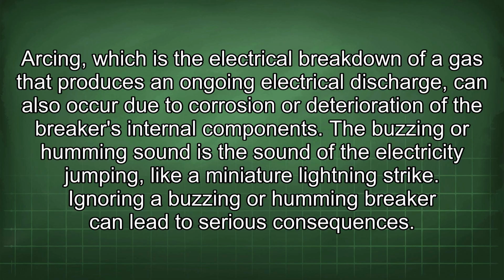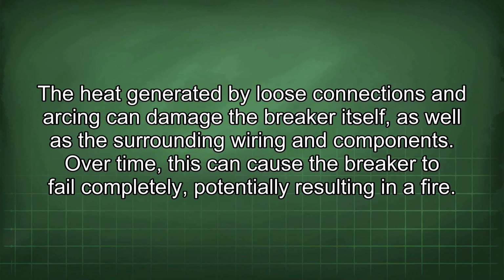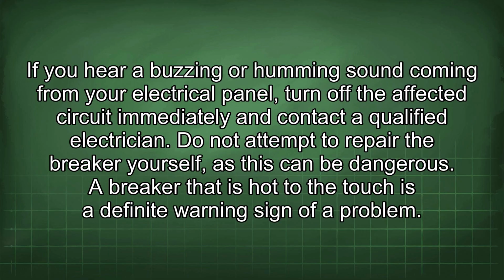Ignoring a buzzing or humming breaker can lead to serious consequences. The heat generated by loose connections and arcing can damage the breaker itself, as well as the surrounding wiring and components. Over time, this can cause the breaker to fail completely, potentially resulting in a fire. If you hear a buzzing or humming sound coming from your electrical panel, turn off the affected circuit immediately and contact a qualified electrician. Do not attempt to repair the breaker yourself, as this can be dangerous.